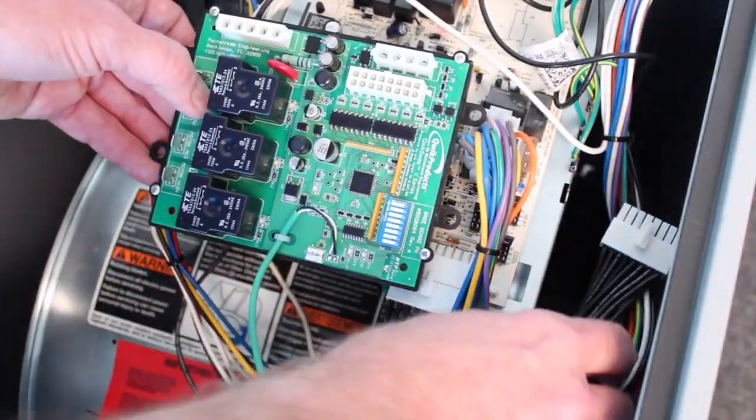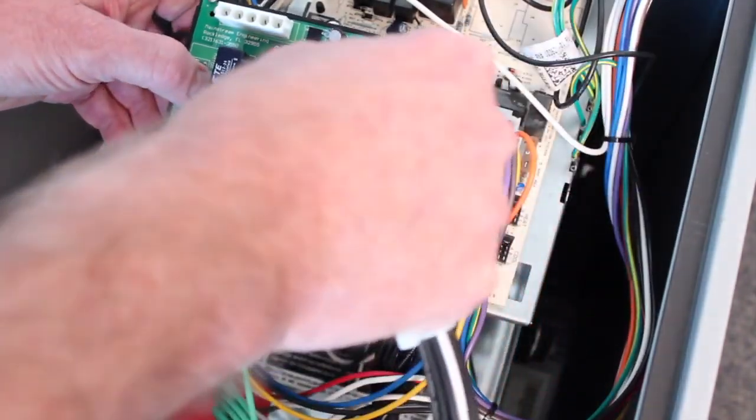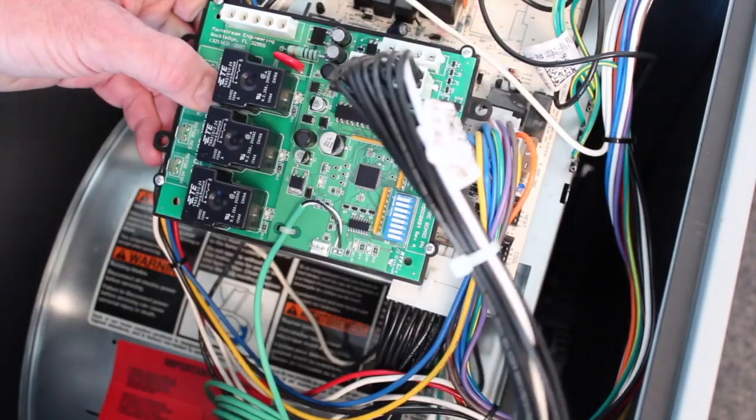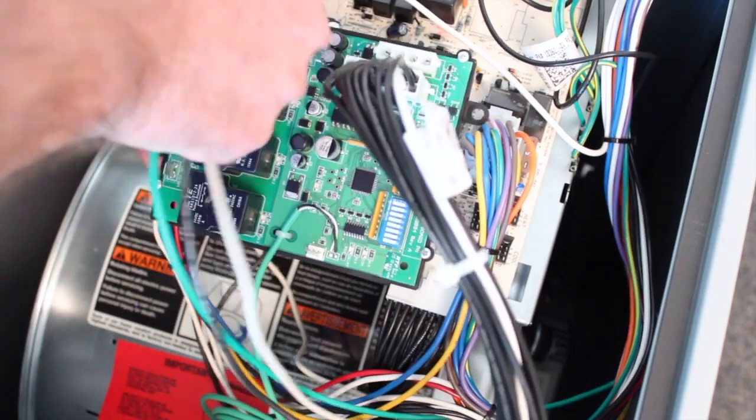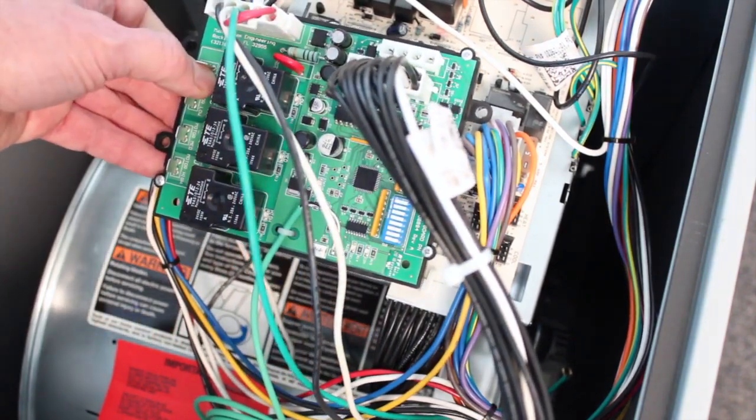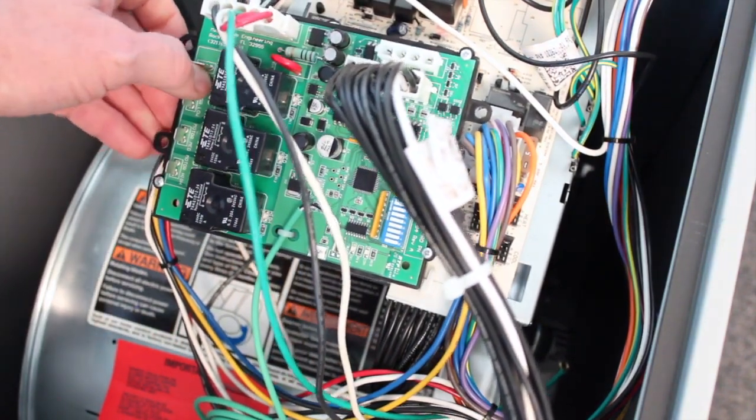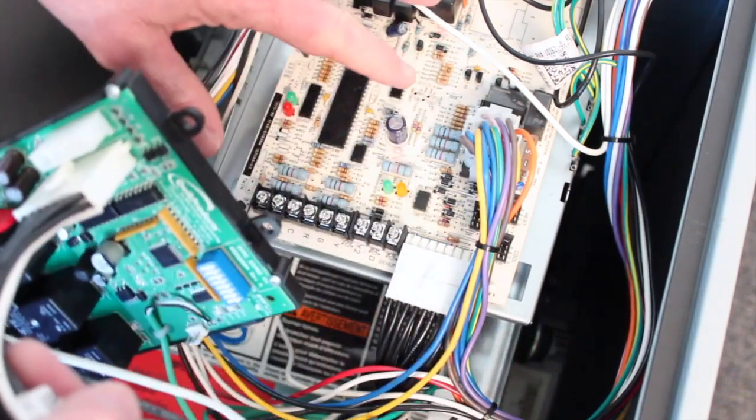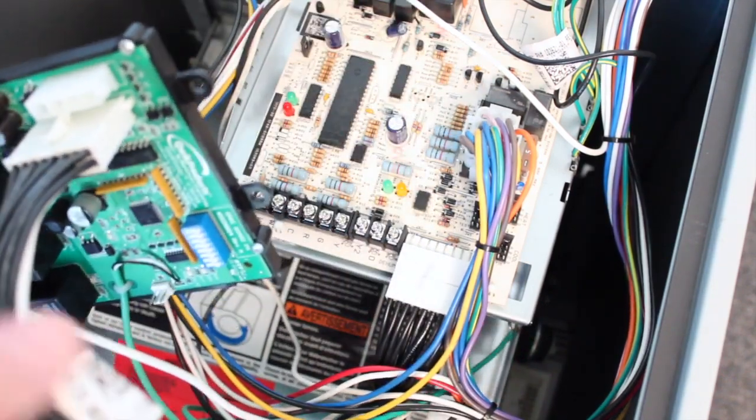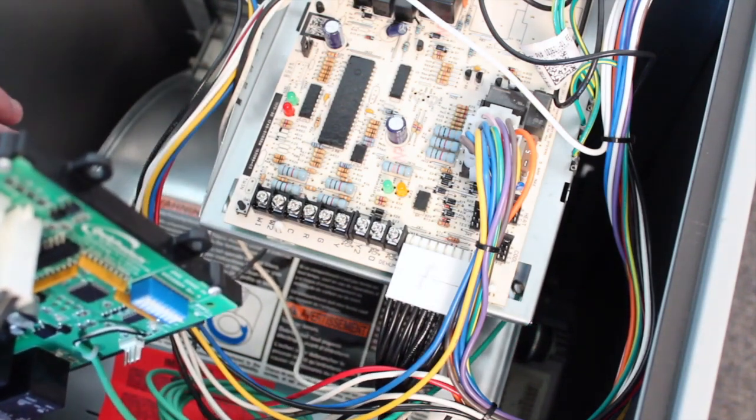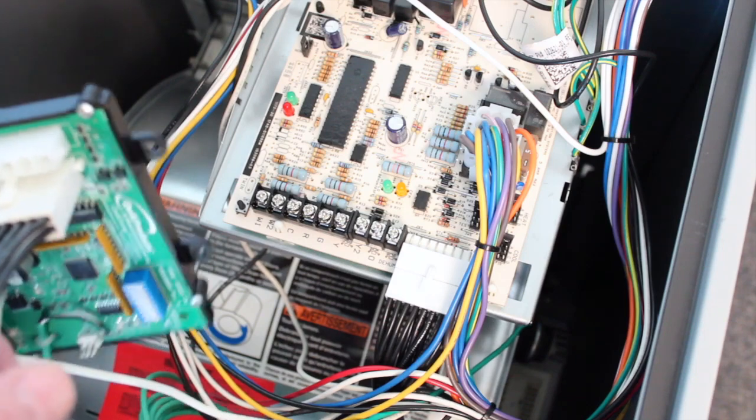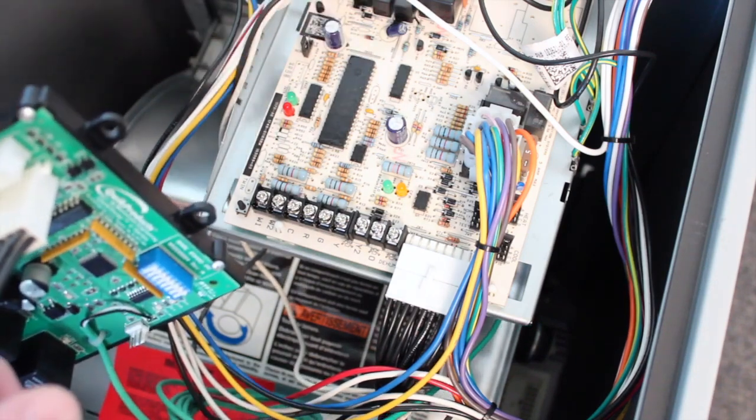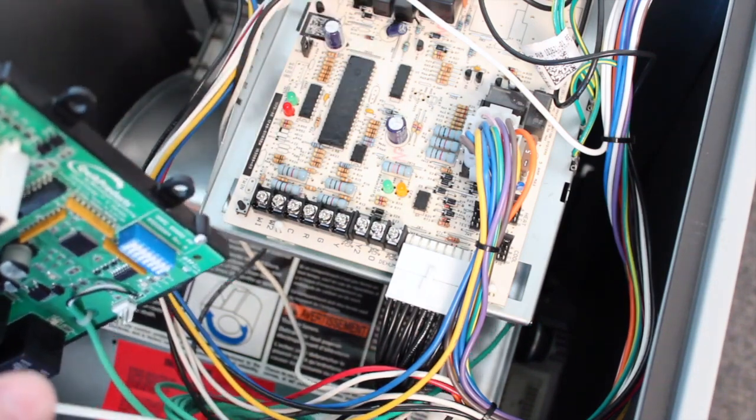Step two is to take the harnesses now and plug them into the QuickSwap board. This is going to allow us to confirm that the QuickSwap board can communicate with the OEM board. As long as it can communicate, then we will proceed with the motor change-out. If it can't communicate, it's very possible that the HVAC control board has been damaged along with the motor.